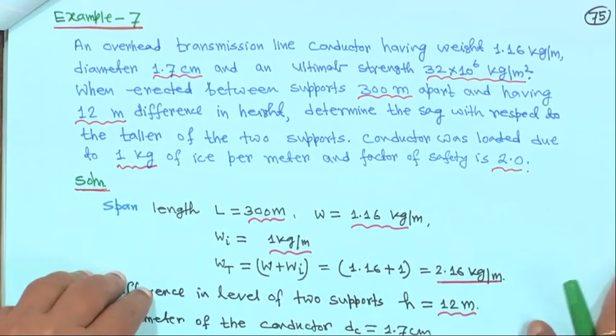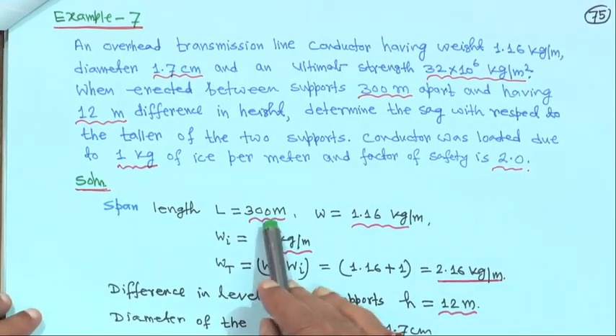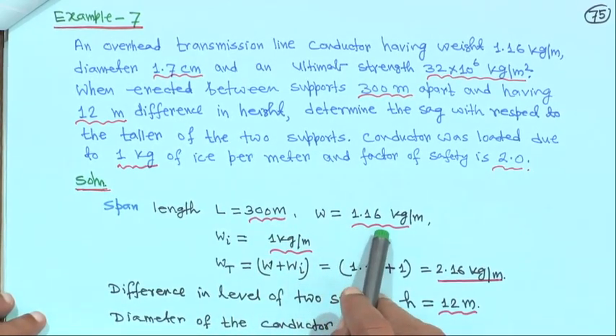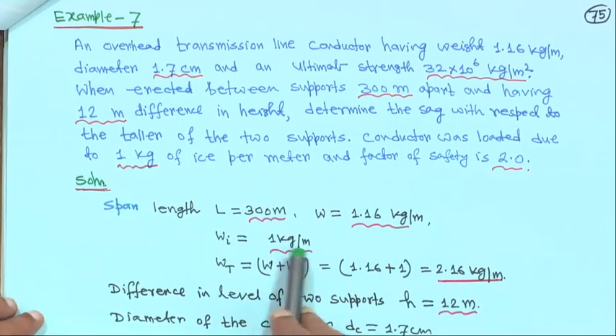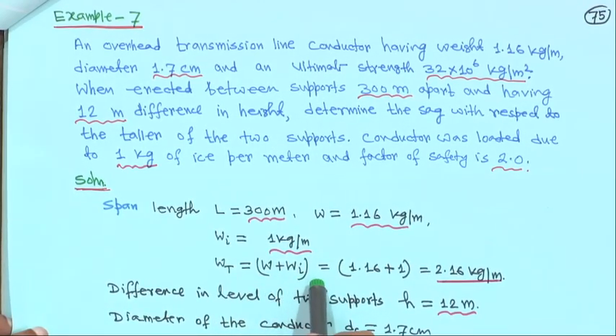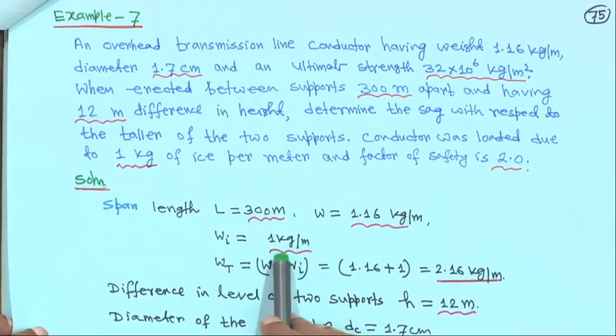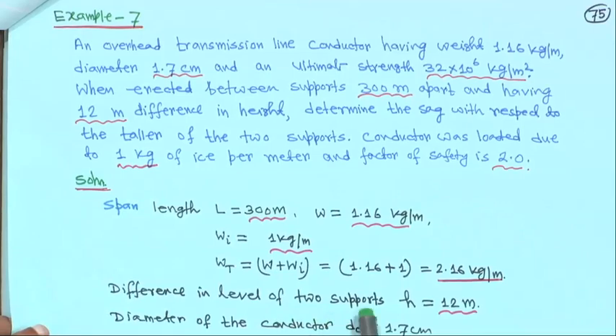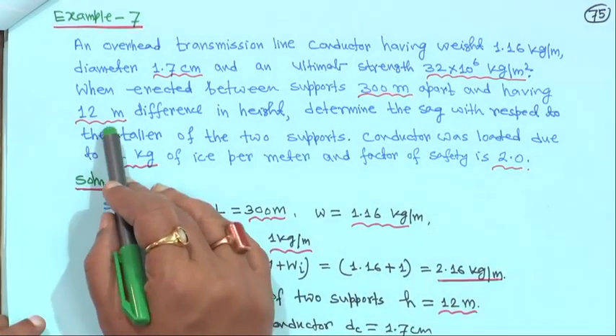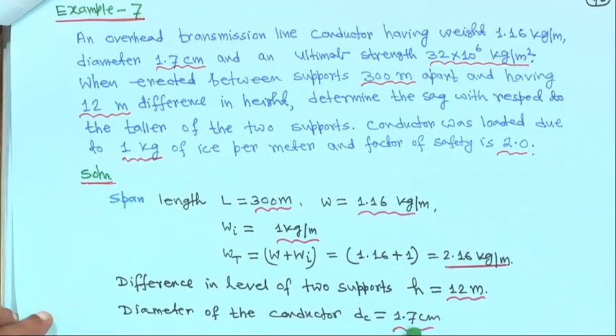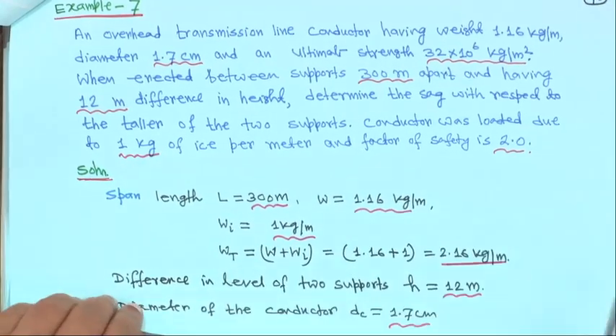Here we are considering ice coating on the conductor. Span length L is equal to 300 meter. W is 1.16 kg per meter and Wi is 1 kg per meter. Total weight Wt is equal to W plus Wi, so 1.16 plus 1 equals 2.16 kg per meter. Difference in level of 2 supports h is equal to 12 meter. Diameter of conductor DC is 1.7 centimeter.